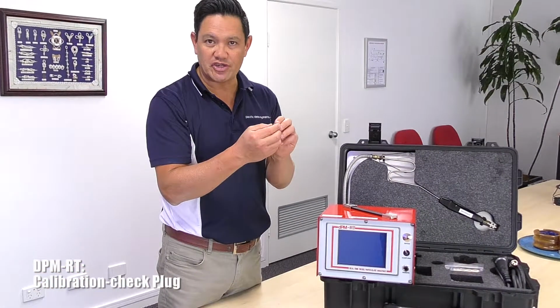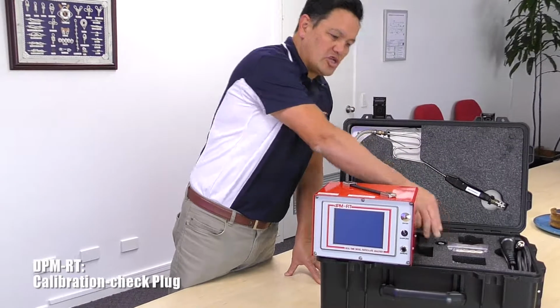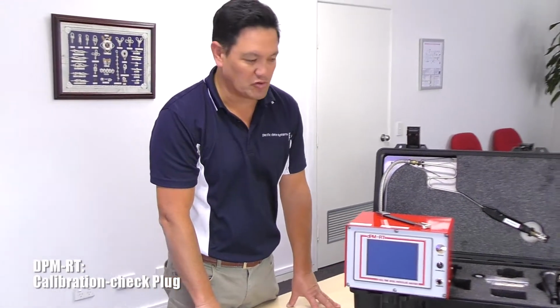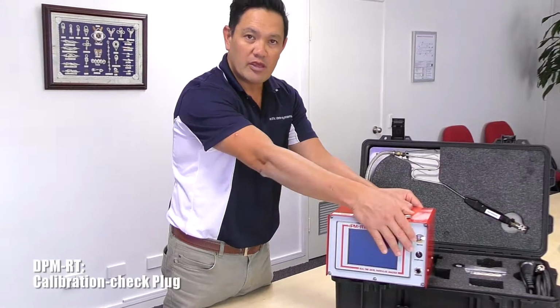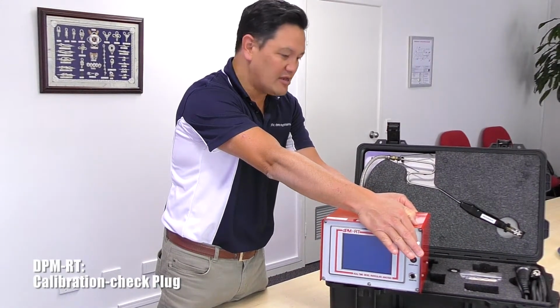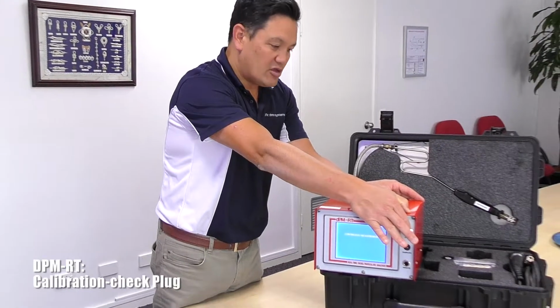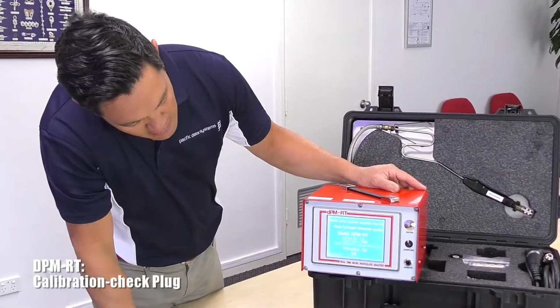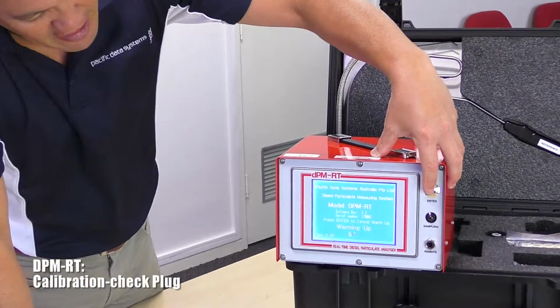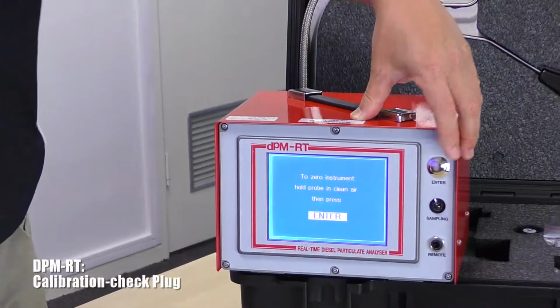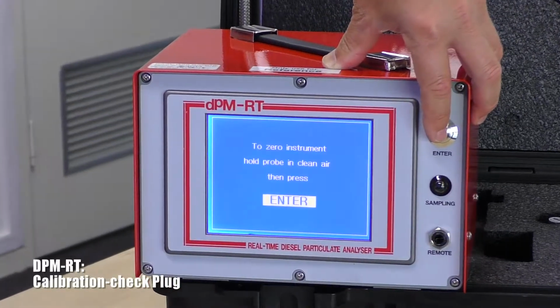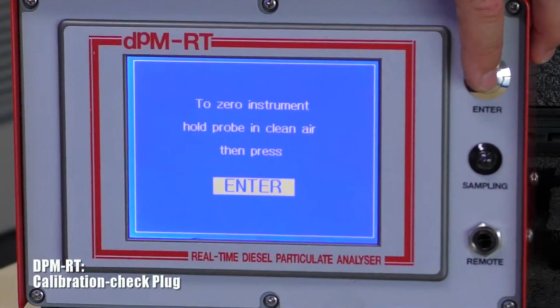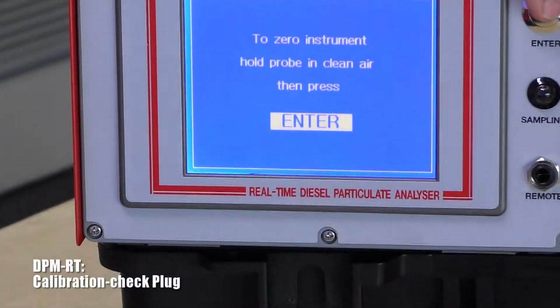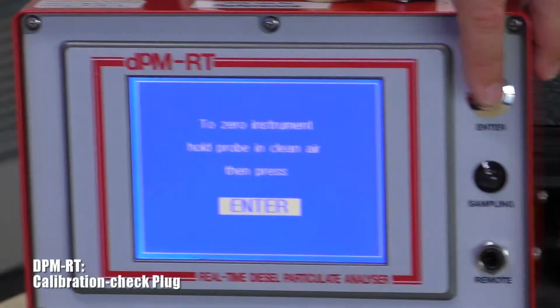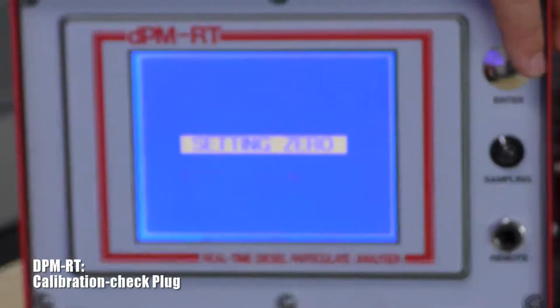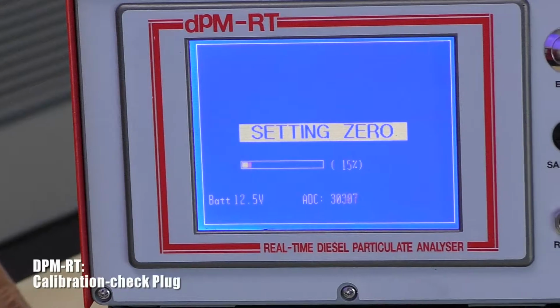Before we insert the calibration check plug, we need to switch on the instrument into continuous mode. If you recall, whilst pressing the enter button in, switch the instrument on, you'll see that it will go into the warm-up screen again. Select the enter button and then make sure that the instrument and the probe is in clean air. For demonstration purposes, we don't have the probe connected, so I'll select enter. The zero will take place.